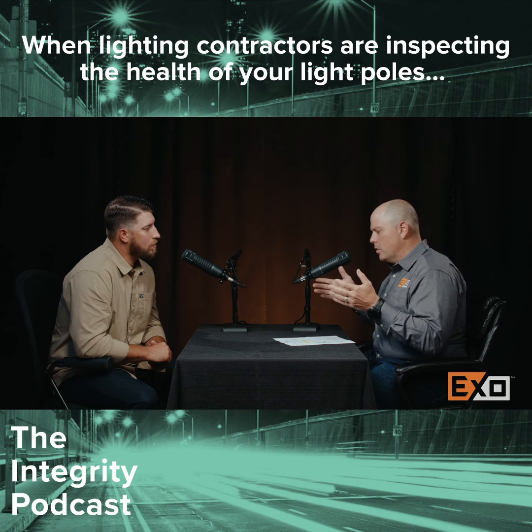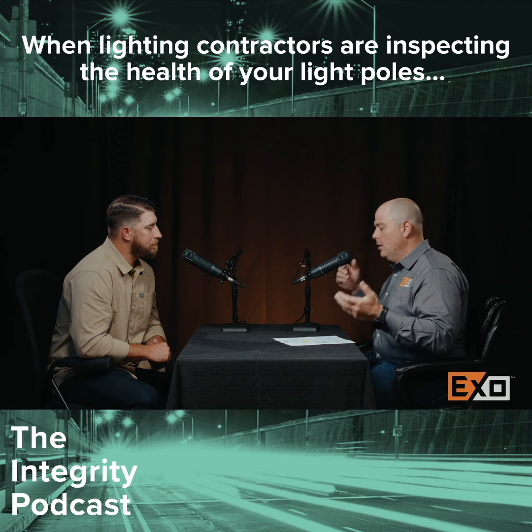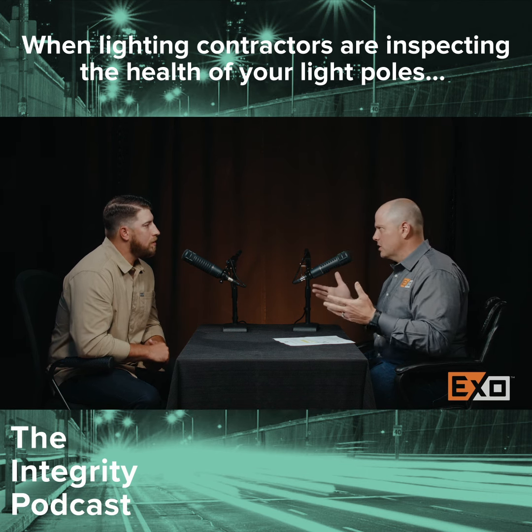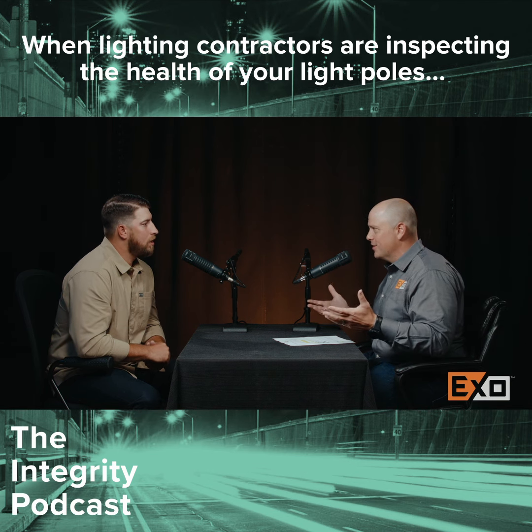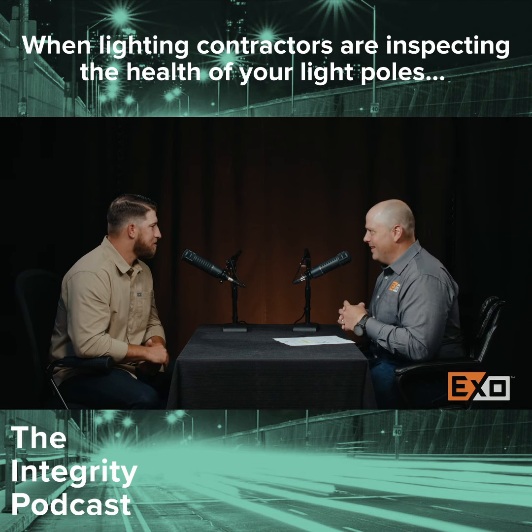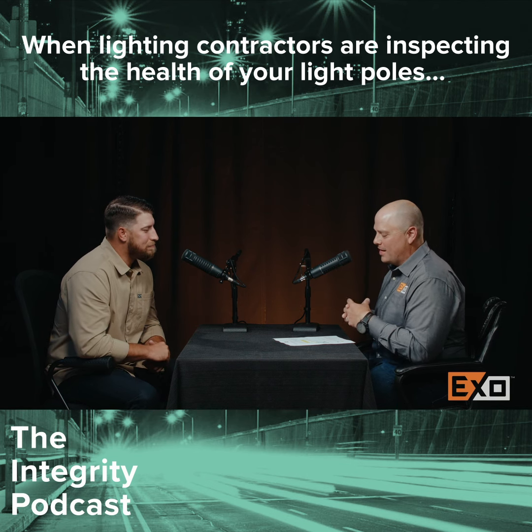Sometimes we see the lighting contractors come in and say everything's fine. Let us go put LEDs on. And they're not fine. Like you said, I think we find on average 6, 7, 8% of poles are ready to fall down, which is a pretty scary statistic, right? Count the number of poles you drive by when you go home today and then add that 6-7%. You're driving by several that are ready to fall down. Absolutely, which is a scary proposition.